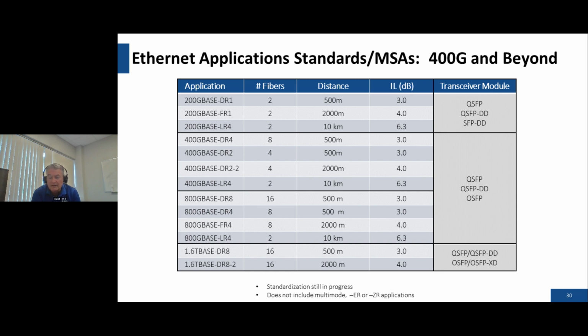One thing to keep in mind: in a lot of cases, going to higher speeds in an effort to keep the cost of transceivers down, these tend to need higher fiber counts. This is one of the reasons, as Manja went through the different connector types we're seeing, we're seeing a bigger push towards the MMC 16-fiber connectors. They can support basically a transition from some applications that need 4 fibers, to 8 fibers, to 16 fibers. So we're continuing to see more of these very high density connectors, with the anticipation that they're going to be used to support even higher speed applications.